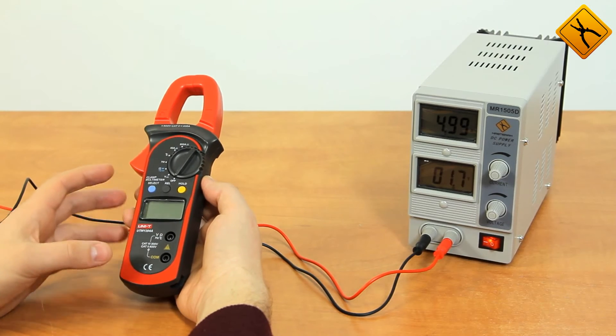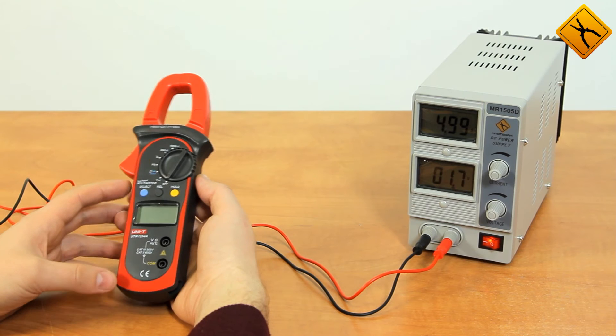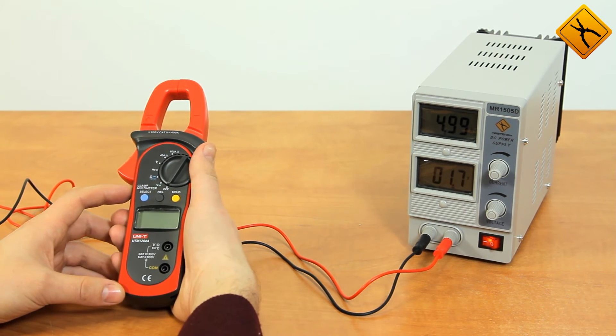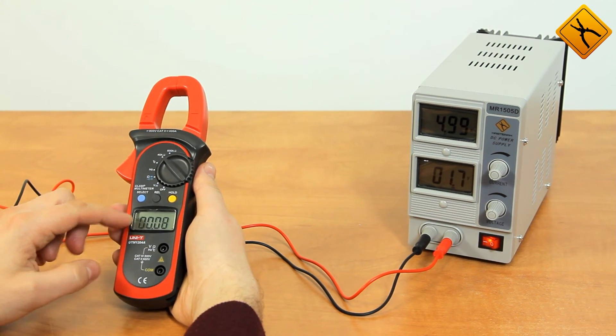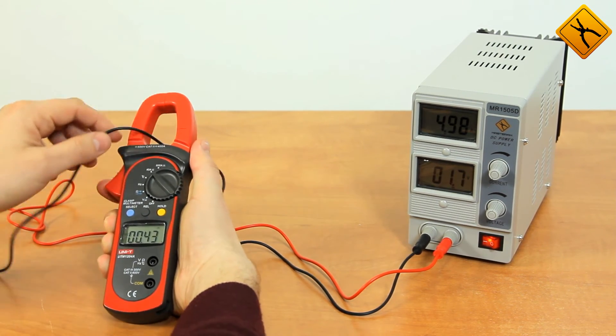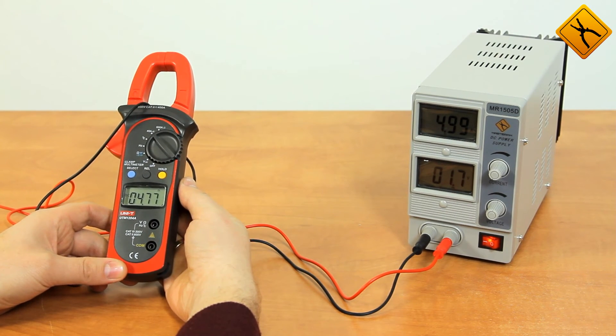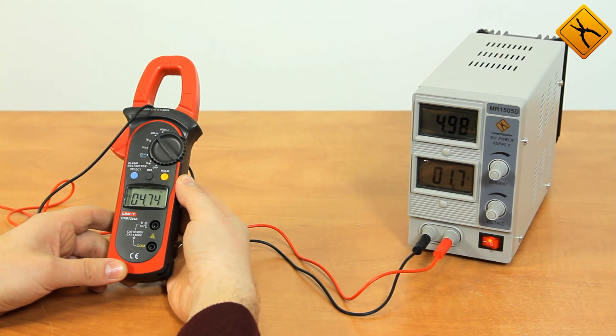This digital clamp meter is very precise at measuring direct electric currents. Let's conduct a direct current measurement of a 5 amp current intensity. Let's turn the rotary switch to the 40 amp position. The device is already set to the direct current measurement mode. I'm now pressing the relative measurement button and clamping the conductor. As you can see, at a current intensity of 5 amps, the absolute measurement error is about 250 milliamps, and that is quite a good result.